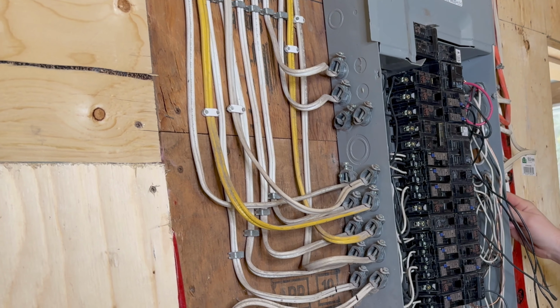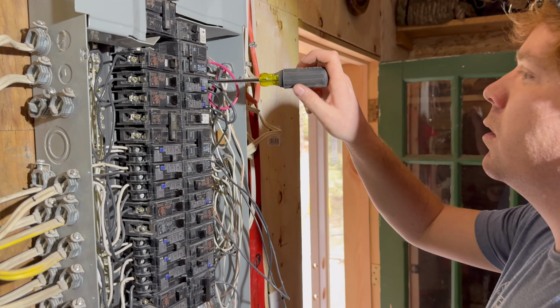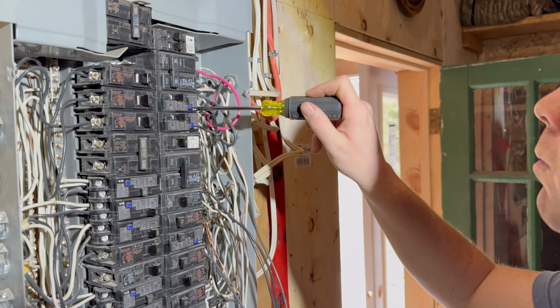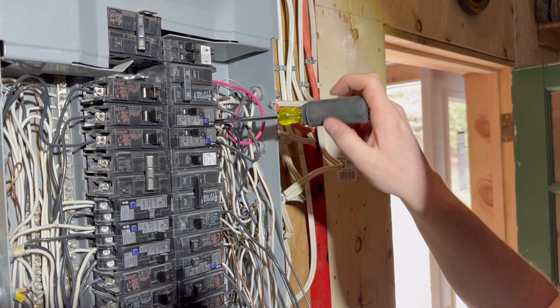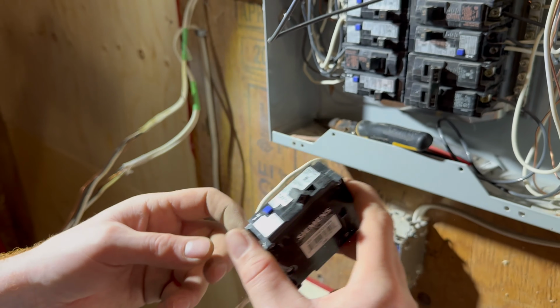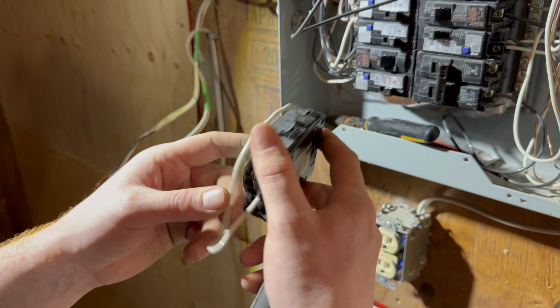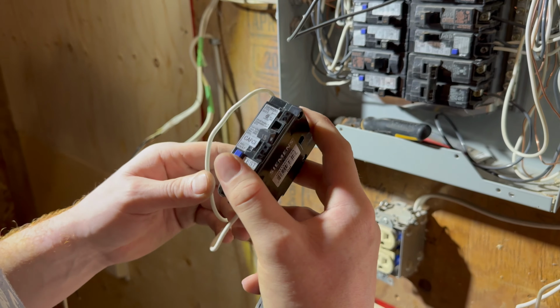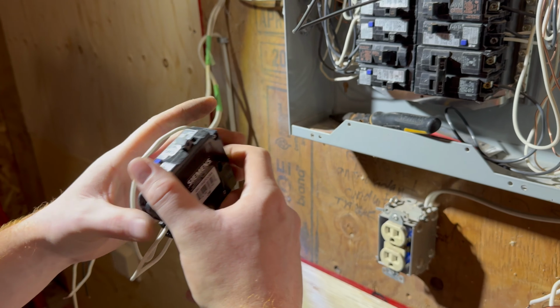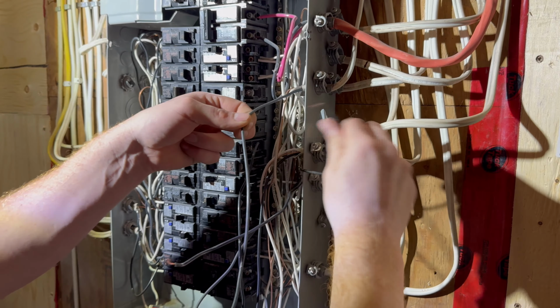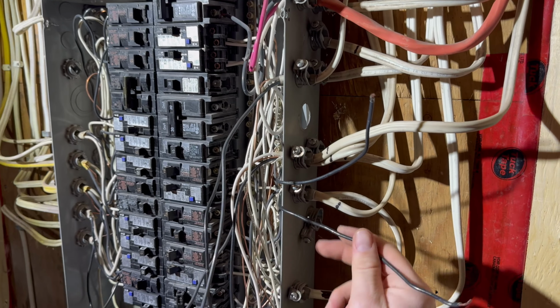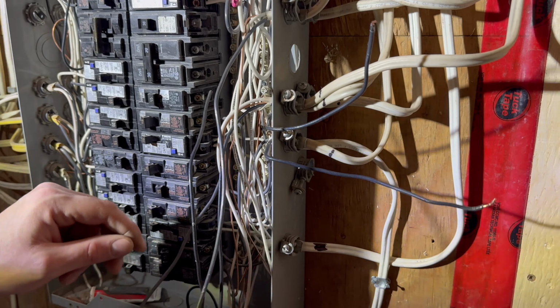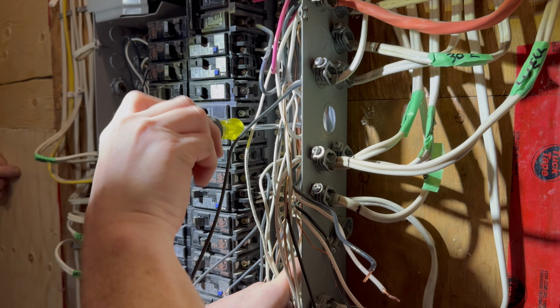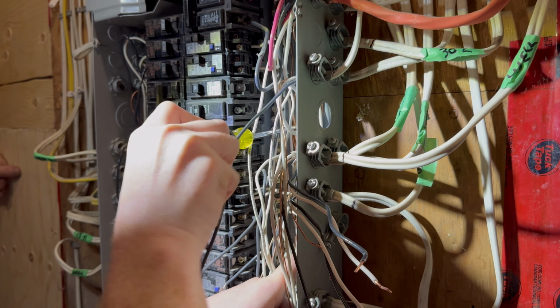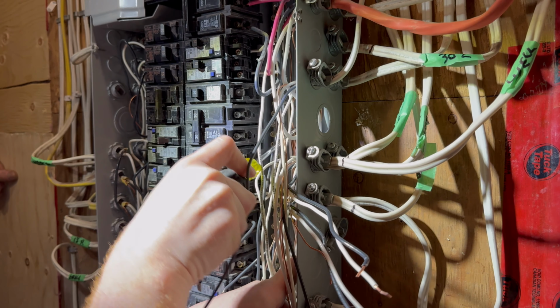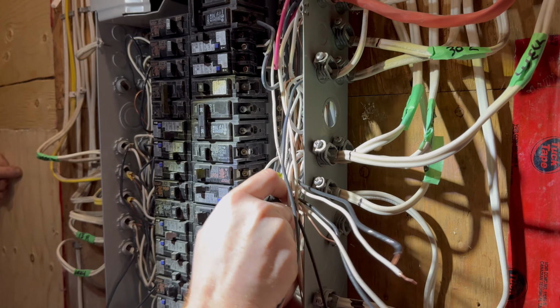If your cables aren't long enough, you may need to install a separate junction box within which the connections can occur. Many jurisdictions require an arc fault circuit interrupter breaker for certain circuits, and that's the case here. The manual transfer switch does not come with arc fault breakers, so Mark is removing that type from the main panel, and he will be putting them into the manual transfer switch.